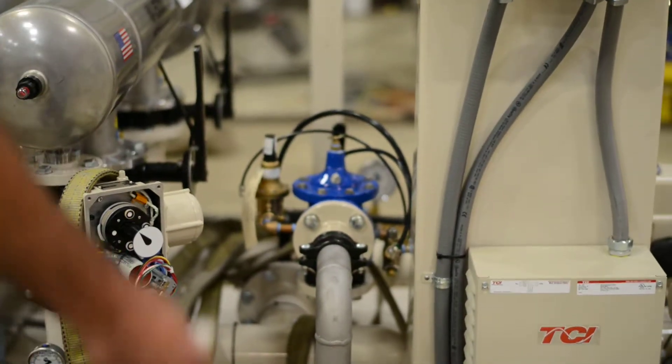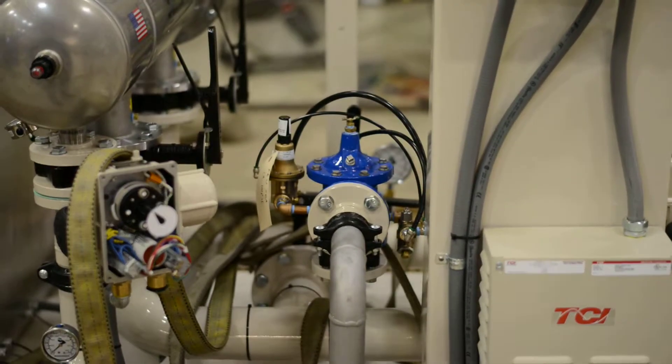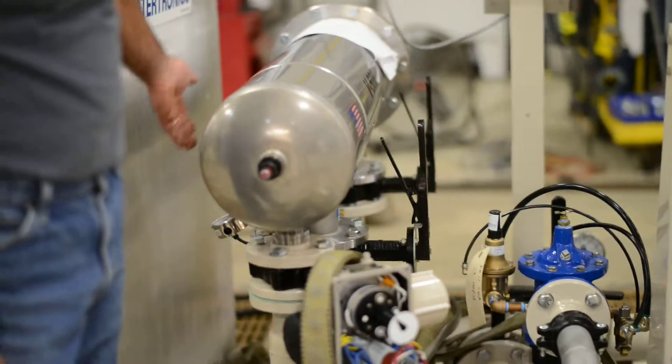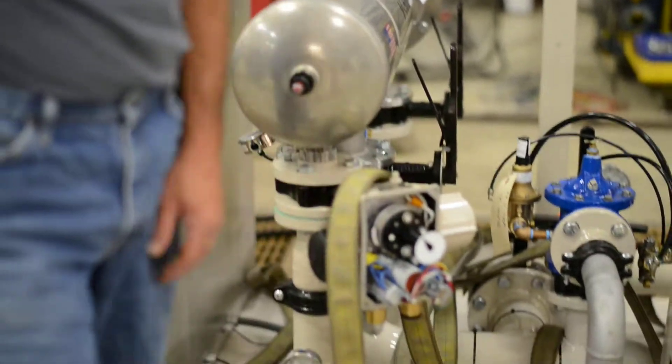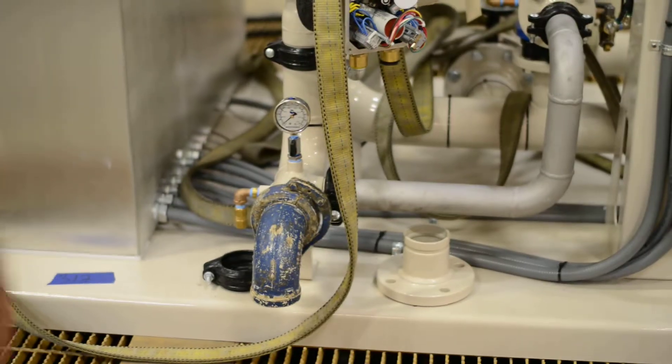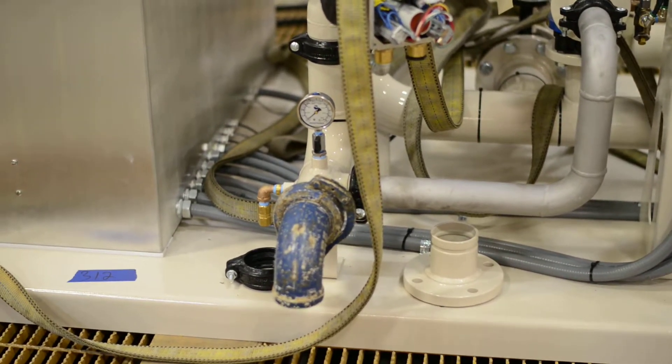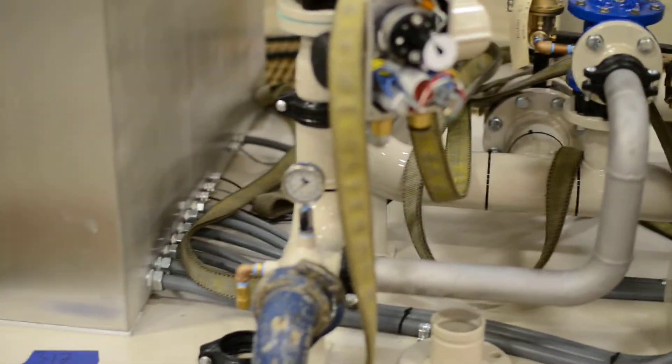What we will do before we ship it is we will drain the PRV and make sure that it is actually turned on so when you fill it up, it fills up with water. Check any connections on here, check all your bolts and fittings, make sure it's tight. Once you throw power on it and get it running, everything should be just fine. This is your flush line up to the filter—make sure that's no flimsy pipe down there. It's got to be really secure.